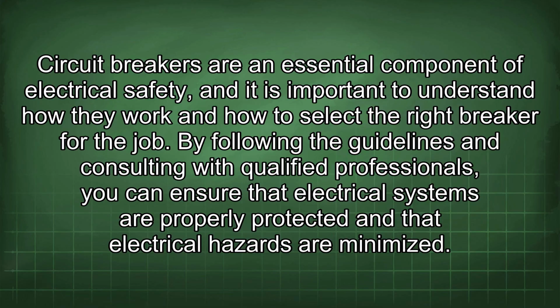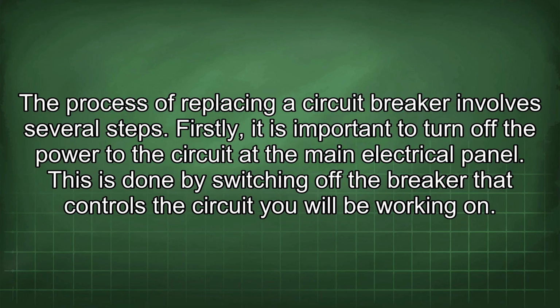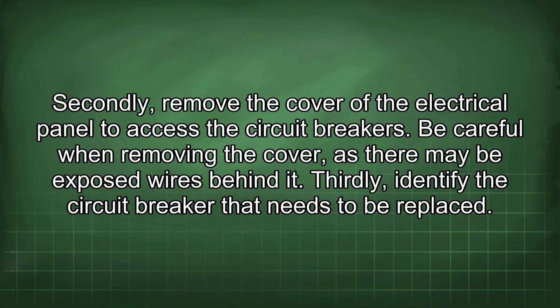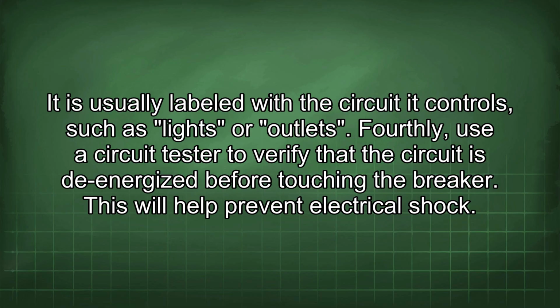The process of replacing a circuit breaker involves several steps. Firstly, it is important to turn off the power to the circuit at the main electrical panel. This is done by switching off the breaker that controls the circuit you will be working on. Secondly, remove the cover of the electrical panel to access the circuit breakers. Be careful when removing the cover, as there may be exposed wires behind it. Thirdly, identify the circuit breaker that needs to be replaced. It is usually labeled with the circuit it controls, such as lights or outlets.